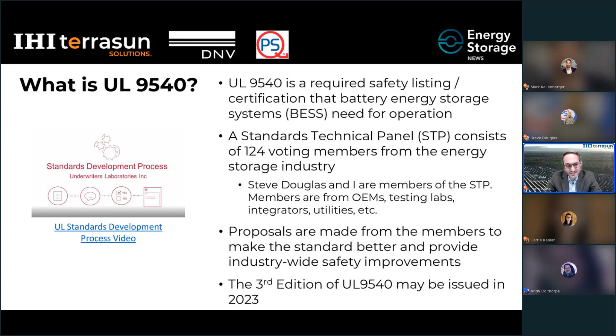What UL 9540 does is it ensures that battery energy storage systems meet the major electrical safety codes for site safety and personnel safety. Those include NFPA 70, which is the National Electric Code, NFPA 855, which is the standard for the installation of stationary energy storage systems, and that one in particular has now become the nationally accepted code that local and state jurisdictions can reference. And then, of course, the International Fire Code.